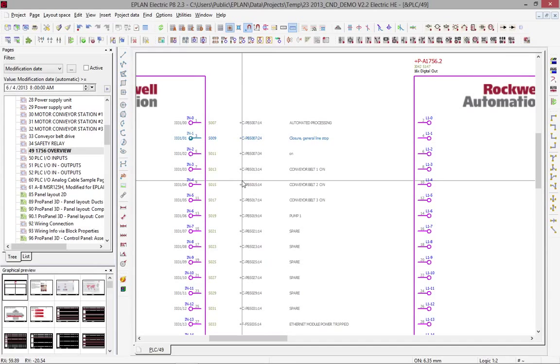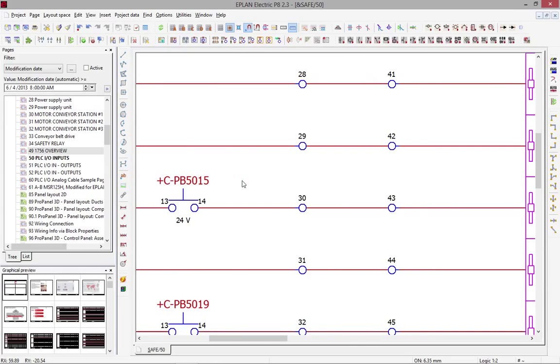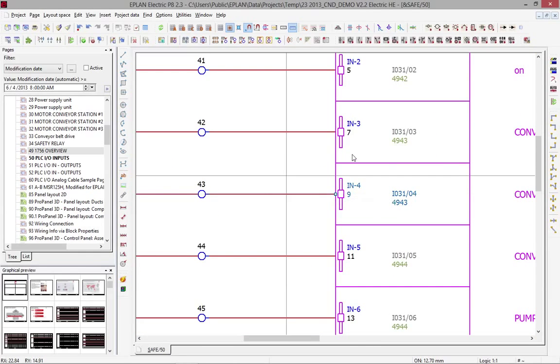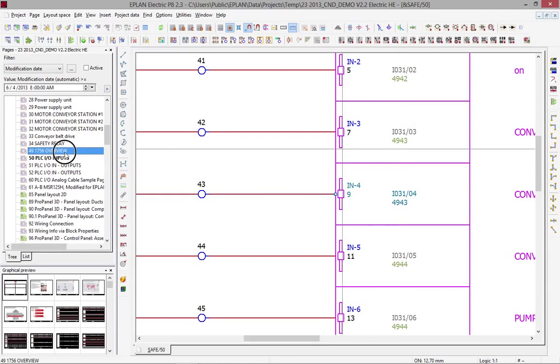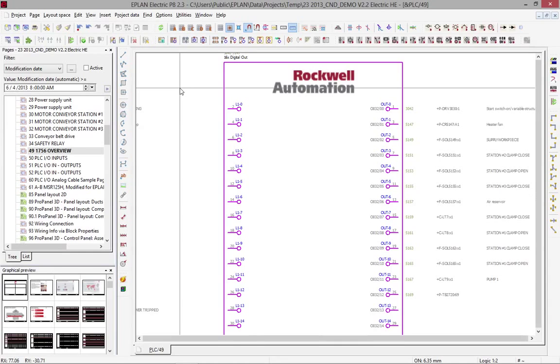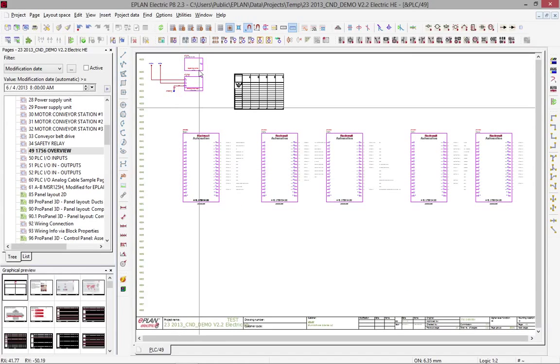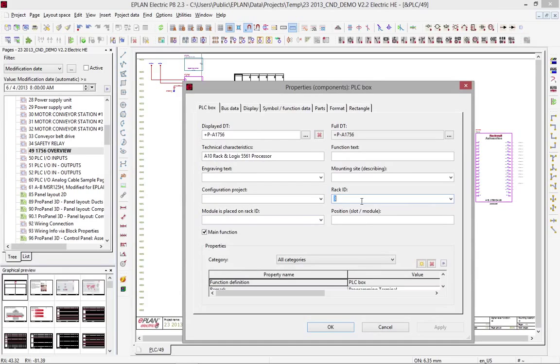So let's take here the pin number 3 on this card. We jump over and we can see here the PLC itself, the pin number 3 with the same IO address. Now, what happens if, for instance, you change this whole page here and you say, okay, this complete rack that was actually set right now to rack ID number 3, I'll actually change it and I'll move it a little bit, and it's actually going to be rack number 05, let's say, or even, whatever, 5. This means you change the rack ID from 3 to 5.